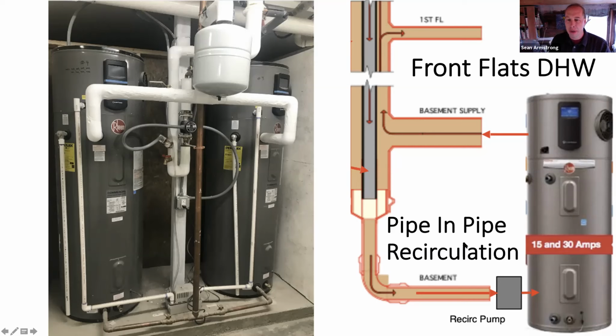Going straight up, they run the pipe with recirculation: water leaves, goes up through an insulated pipe delivering water, and at the top it just bends around rather than exploring the rest of the building, turning straight back down inside the same insulated sheath so it doesn't lose heat. In a recirculation system you can lose a third to an equal amount of the heat you're delivering to apartments just in the recirc loop, which can be a dramatic energy suck if the piping isn't well insulated. This straight up-and-down stack style is the most efficient and keeps heat loss to a minimum.